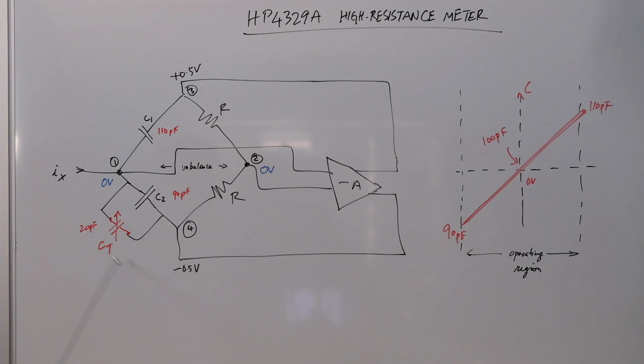So the combination of imbalancing either through the capacitor or current coming in through an external resistor, high resistance, which is in the picoamp region, or a very, very small amount of current, can significantly imbalance this bridge that causes this oscillation, which then is used as a parametric converter. And the parametric thing that you're really using is the capacitance of these diodes. That's why it's called this parametric converter, and that principle is really unique in this particular instrument, and I guess in future instruments that were based on this principle.